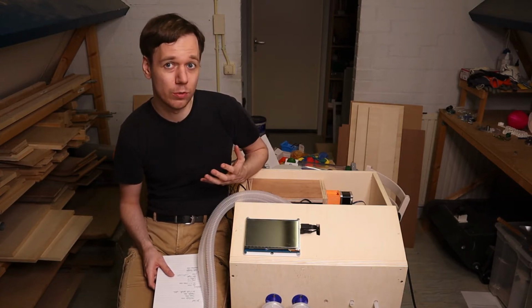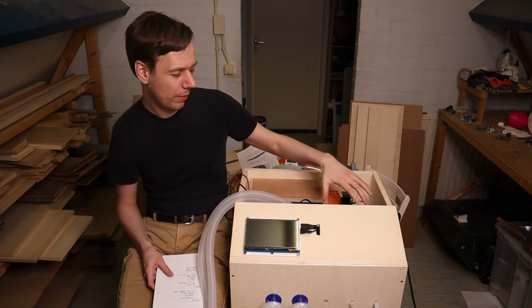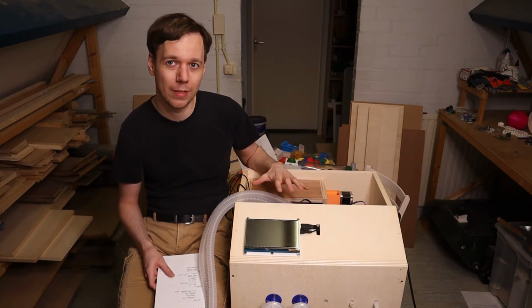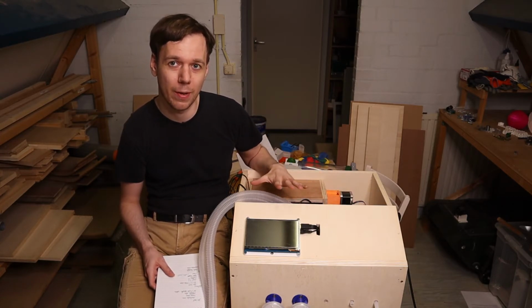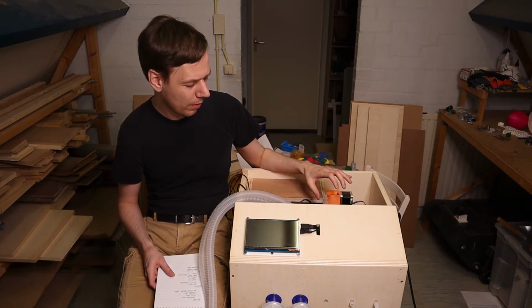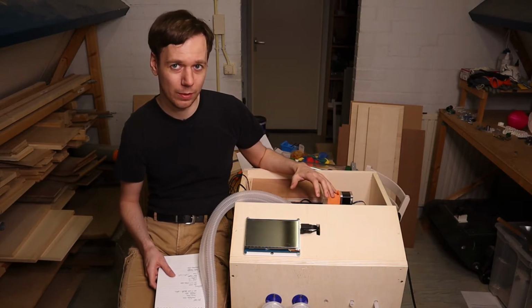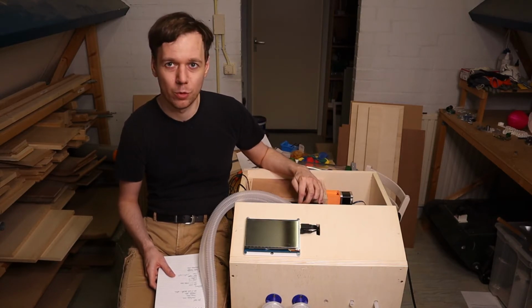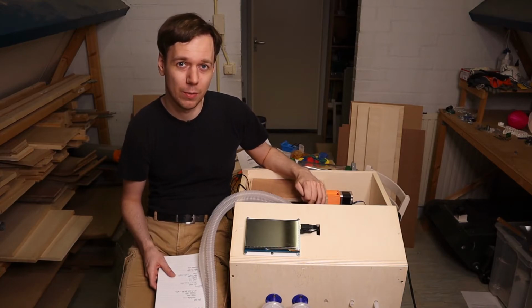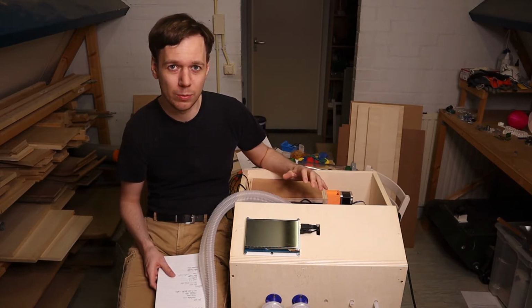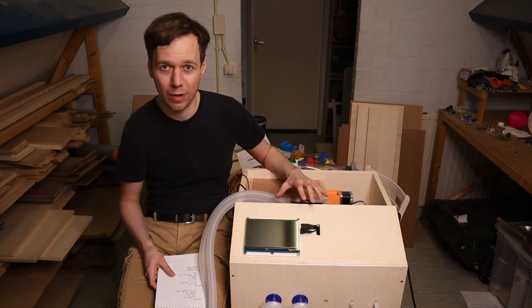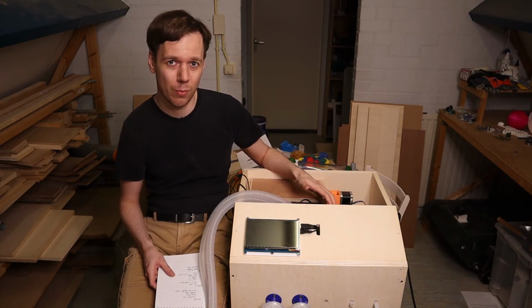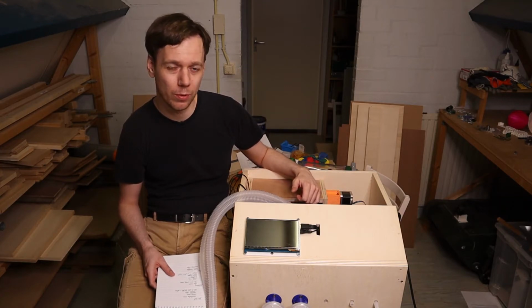On the oxygen concentration, you also have to ensure that all the components that touch the gas are oxygen compatible, and the tubes and fittings, I believe, are. But the valves are not. The valves have aluminium bodies, and those need to be changed out for valves with brass bodies. So I'm looking at brass body semi-direct valves. I'm hoping those are going to work.